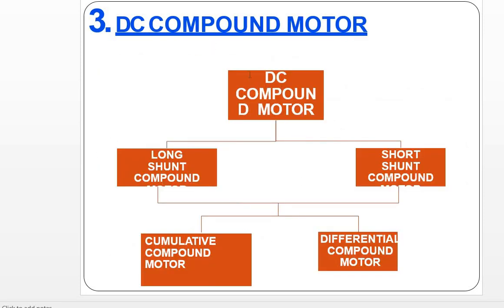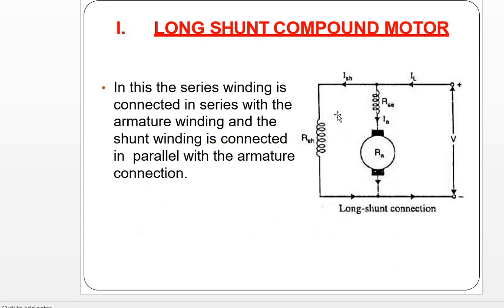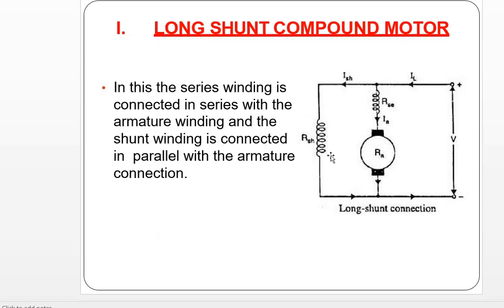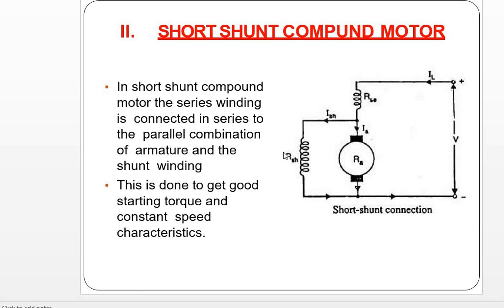Now we are going to talk about the compound motor. The compound motor has both a long-shunt type and a short-shunt type, as well as cumulative and differential configurations. In long-shunt compound motor, the series winding is connected in series with the armature winding and the shunt winding is connected in parallel — combining series and parallel connections. In short-shunt compound motor, the series winding is connected in series with the parallel combination of armature and shunt winding.